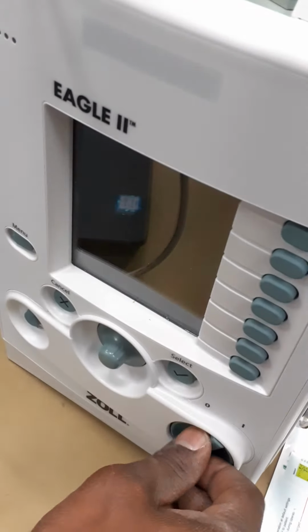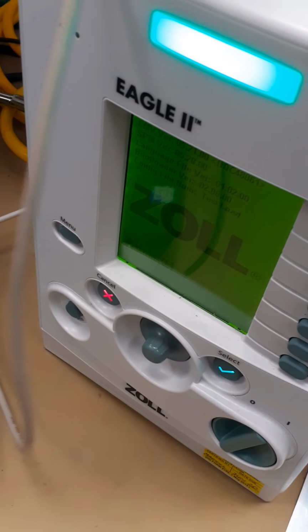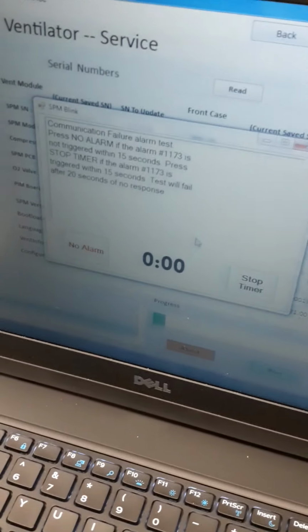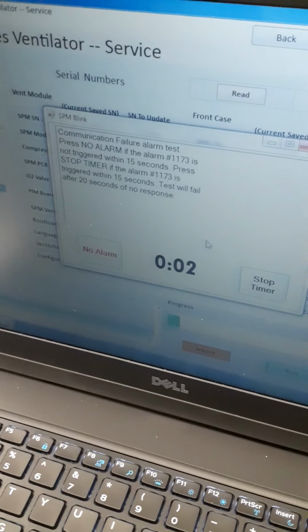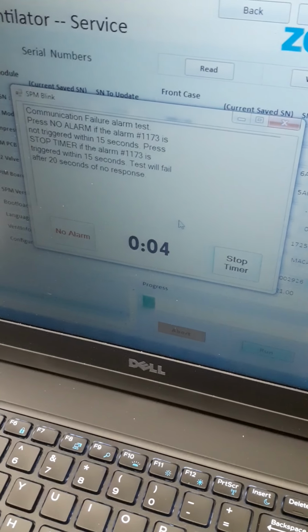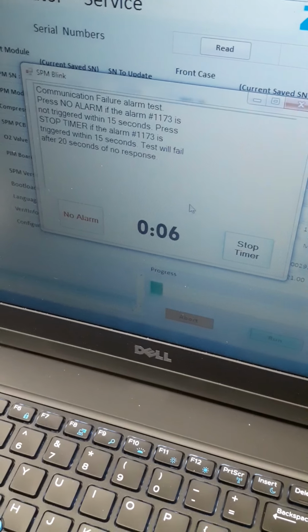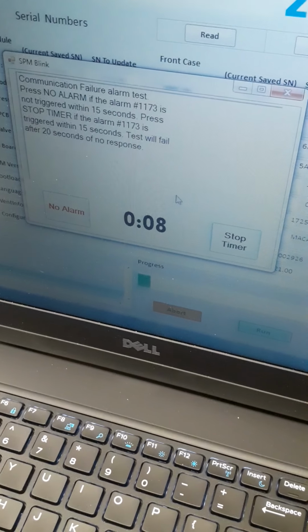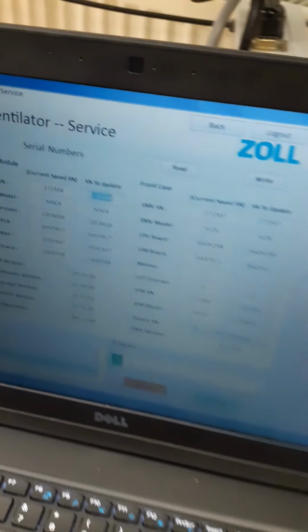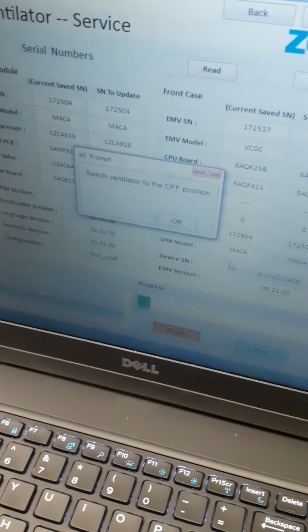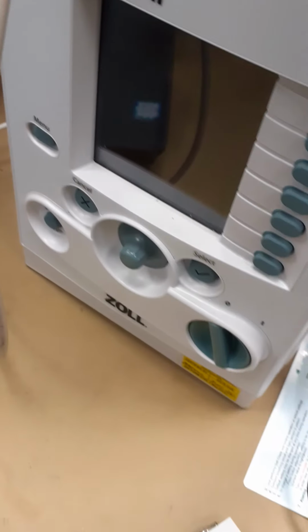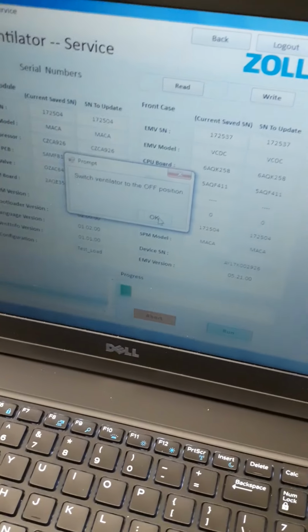Turn the ventilator on. First breath went, hit OK. We're looking for an alarm. Should happen within 15 seconds. There you go. Stop timer. Pass. Switch the ventilator off. Press OK.